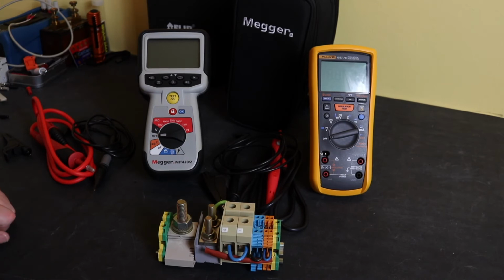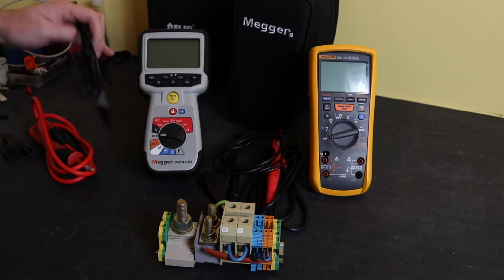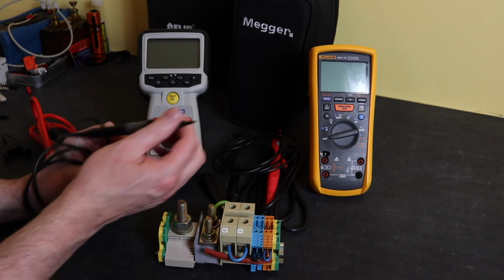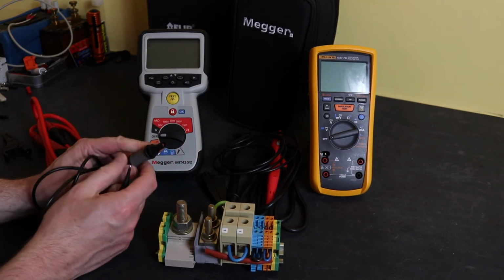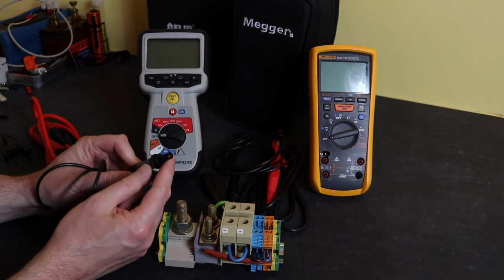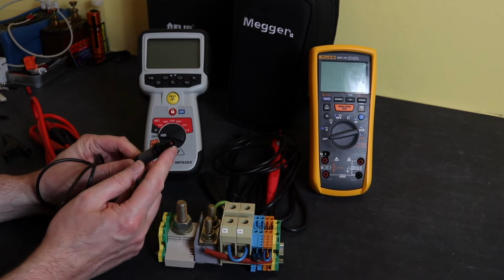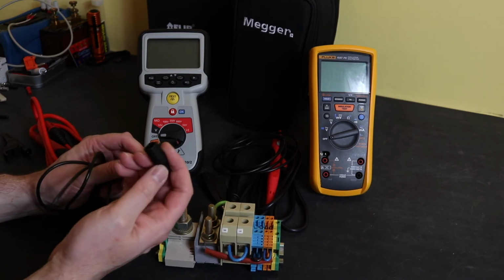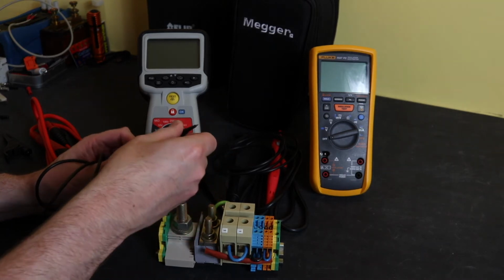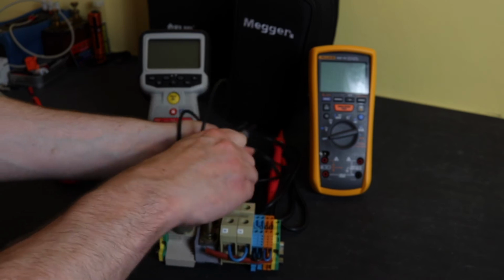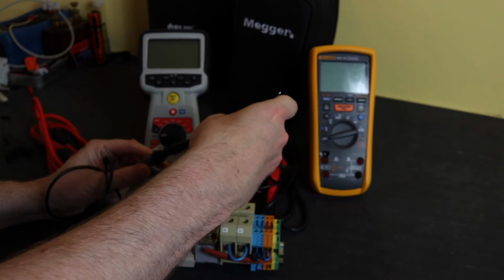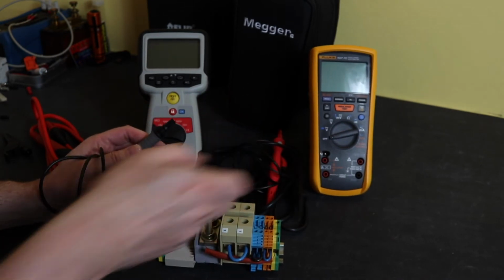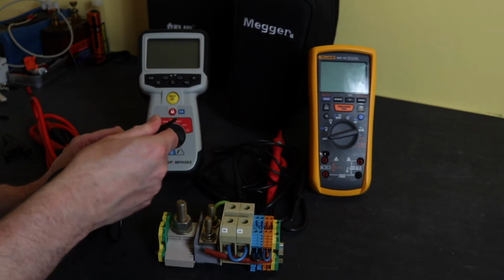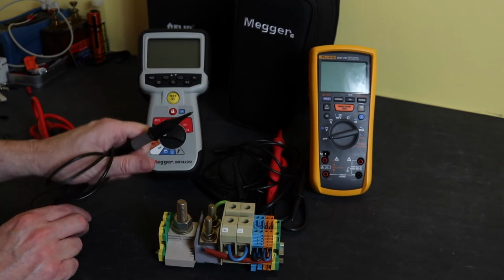Okay, a bit closer look at the leads. The leads from the Megger. The probes, tips and crocodile clips are a unique fixture. There's this little ridge over the probe body here that the actual tip clips onto, so a standard 4mm accessory will not clip over that and so won't work with this, so you're stuck with the items. You can see the Fluke doesn't go on at all, and so you're stuck with the accessories offered by Megger there really.